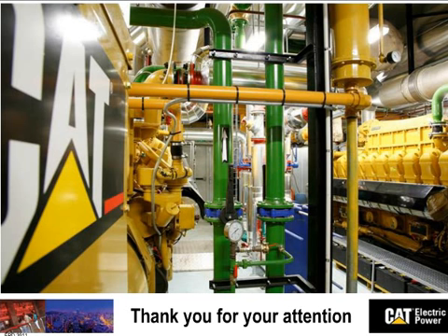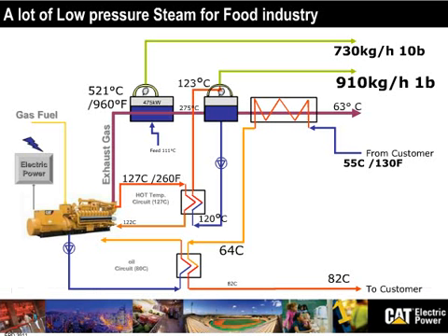I have a couple people, Francois, asking questions about lower temperature steam. So one specifically from Kevin Reinhardt of Omnova is, can I produce 200 F steam with, say, a 1.5 megawatt genset? Yeah, and that's exactly the slide I brought up earlier in the conference. It's the beauty of using our hot ebullient cooling gensets that have jacket water temperature at 127, which is 260 F, and you can do a lot of steam at low pressure and then low temperature, and that's what is used very frequently in the food industry, but in other applications as well.